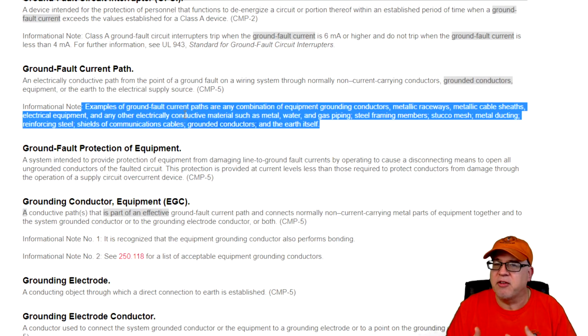So we have certain things in the code under 250.118, but don't worry, we'll get there, that talk about what is considered a low impedance path. Okay, so we've got raceways: RMC, IMC, EMT. We have the equipment grounding conductor, whether it's bare, covered, or insulated, in different types of wiring methods like non-metallic sheathed cables and SE cables, or SER, I should say. It's also in SEU if you're going to use it out to a piece of equipment like an air handler and only need 2 hots and an equipment ground, then you could still use SEU for that. All of those are designed to create a low impedance path.